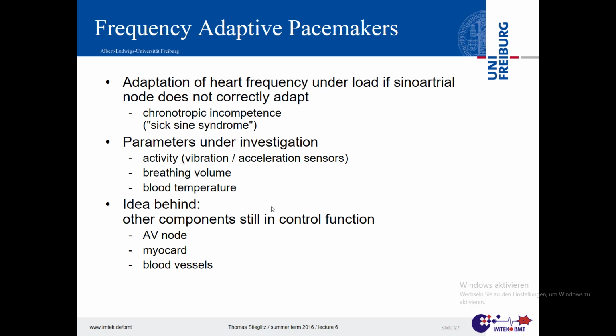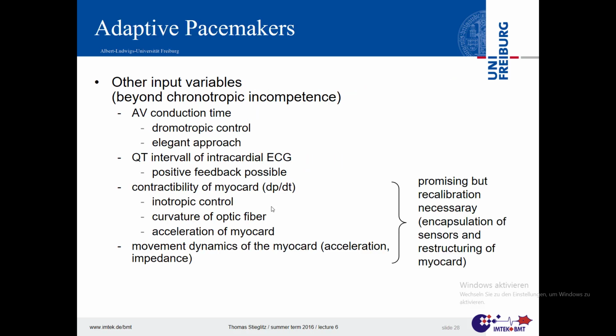And the idea is to get as much out of those secondary parameters as you can, to put into algorithms to adapt your heartbeat. And then it comes to research, where people say, well, I can monitor the atrioventricular conduction time and see what the system behind already does, and I can adapt the stimulation to that. And the QT interval, so QRS-T, that interval, if you measure that, that is one of the indicators for psychological load. So if you measure that, you get an idea if you should tweak a little bit on the frequency there.